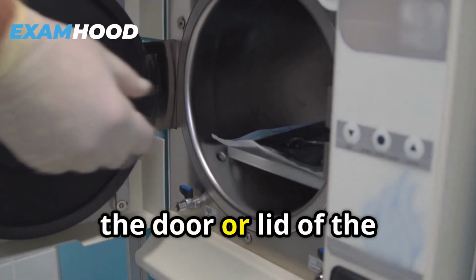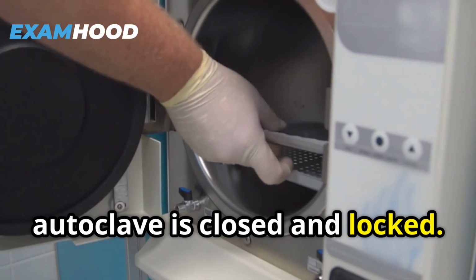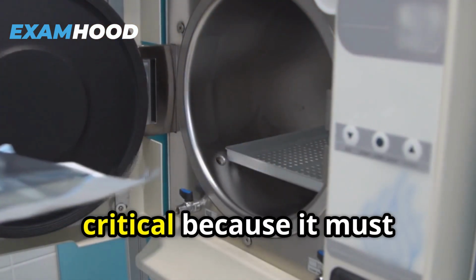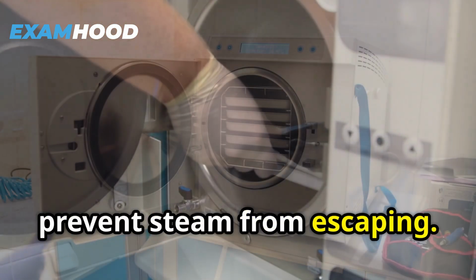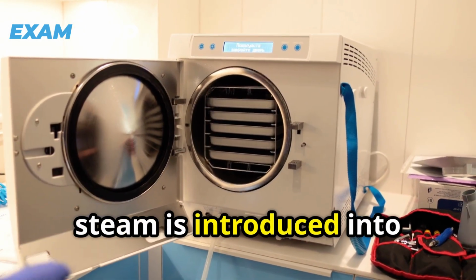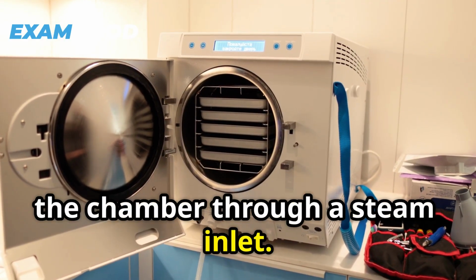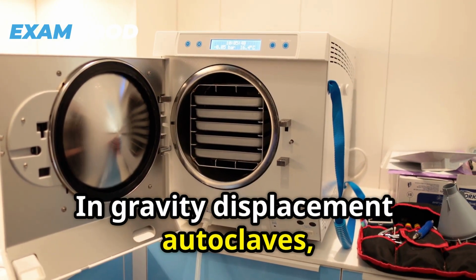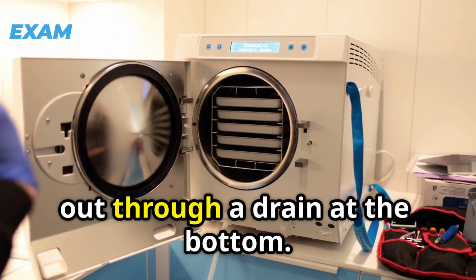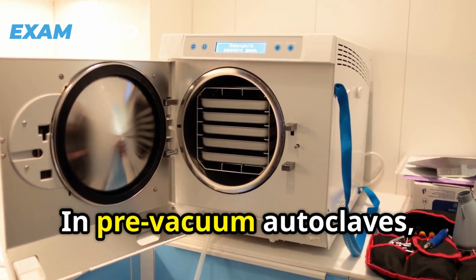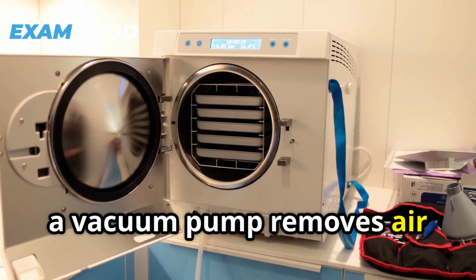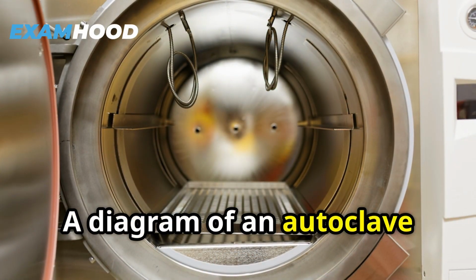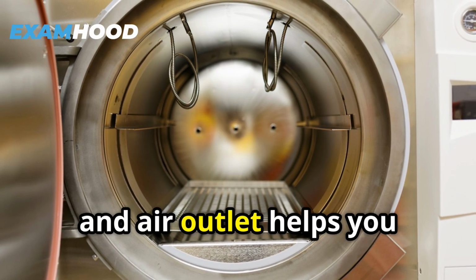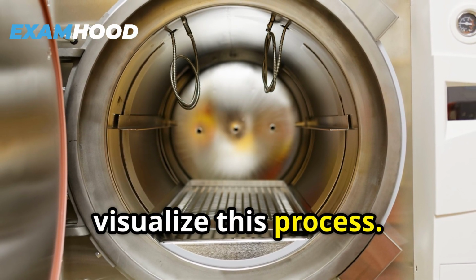Next, the door or lid of the autoclave is closed and locked. The sealing mechanism is critical because it must withstand high pressure and prevent steam from escaping. Once sealed, steam is introduced into the chamber through a steam inlet. In gravity displacement autoclaves, steam pushes the cooler air out through a drain at the bottom. In pre-vacuum autoclaves, a vacuum pump removes air before steam is admitted, improving steam penetration. A diagram of an autoclave with a marked steam inlet and air outlet helps you visualize this process.